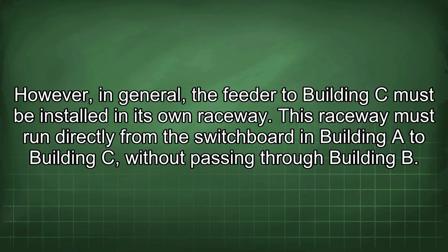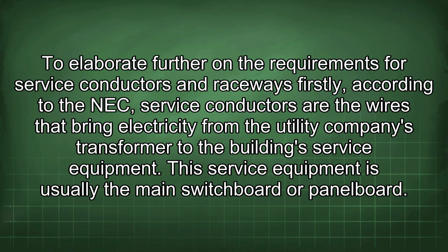However, in general, the feeder to Building C must be installed in its own raceway. This raceway must run directly from the switchboard in Building A to Building C, without passing through Building B. To elaborate further on the requirements for service conductors and raceways, firstly, according to the NEC, service conductors are the wires that bring electricity from the utility company's transformer to the building service equipment. This service equipment is usually the main switchboard or panelboard.